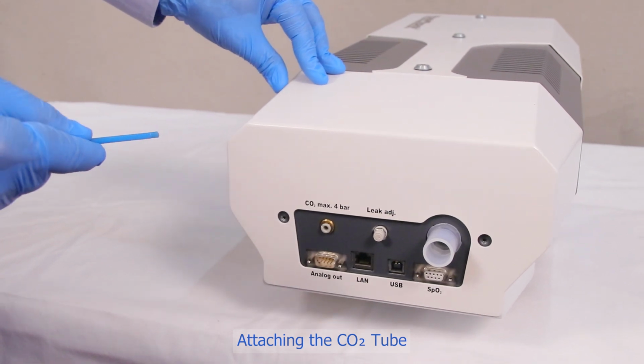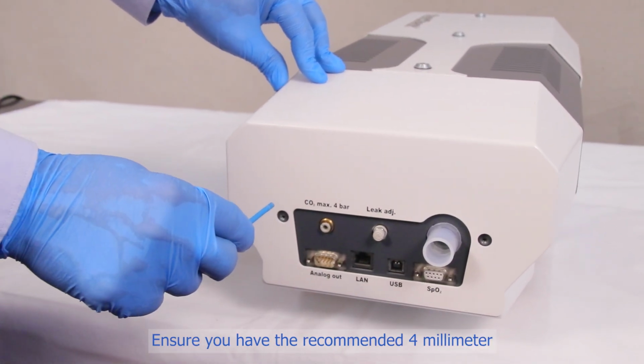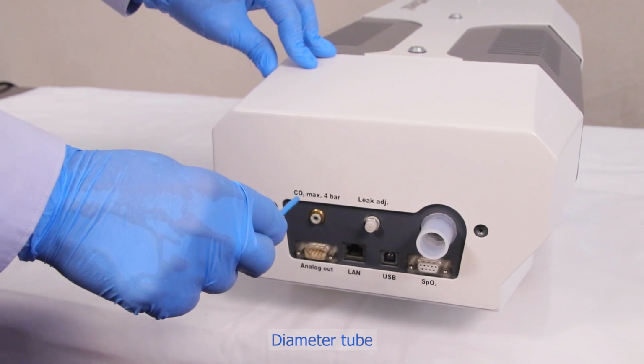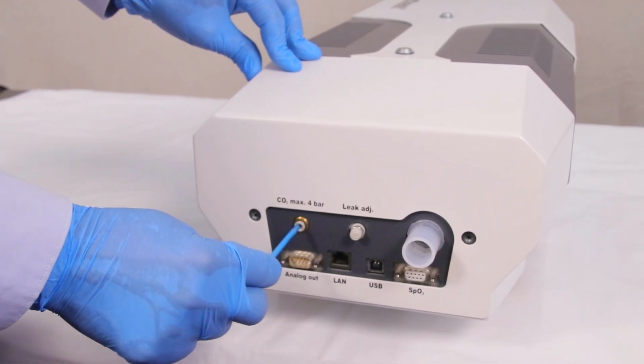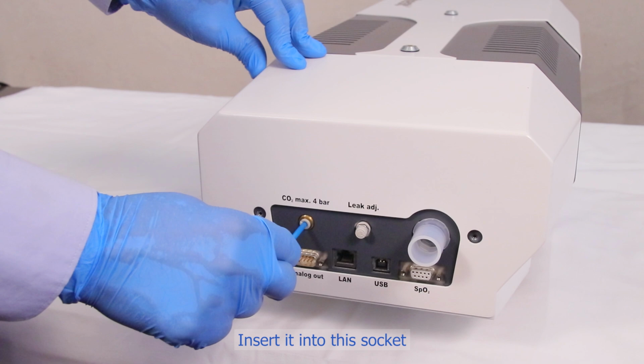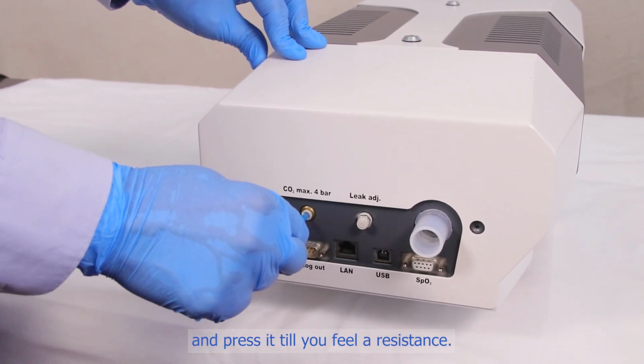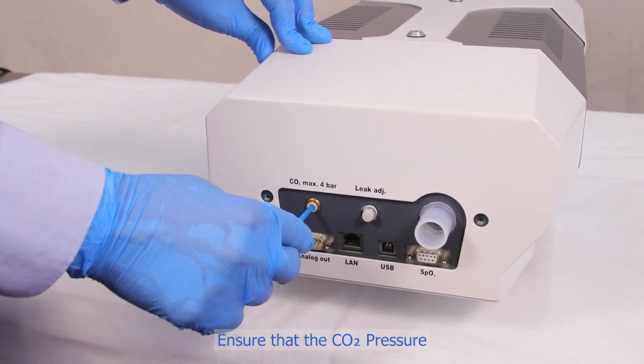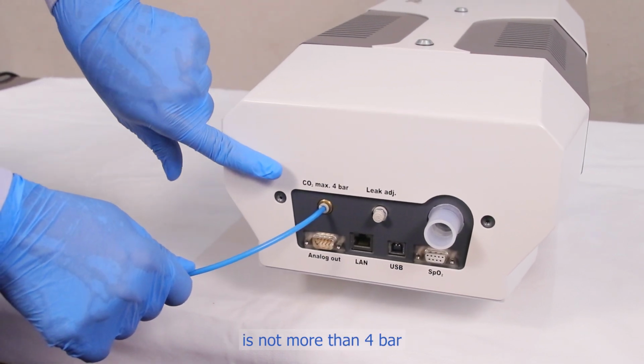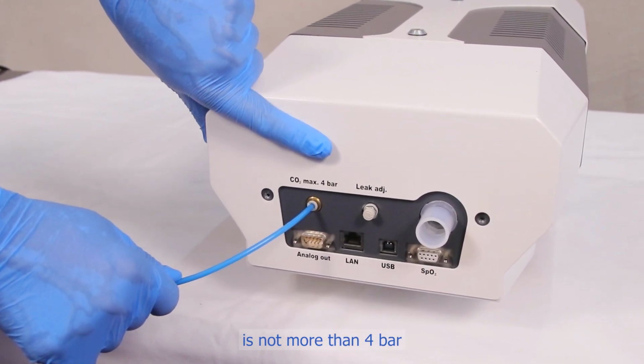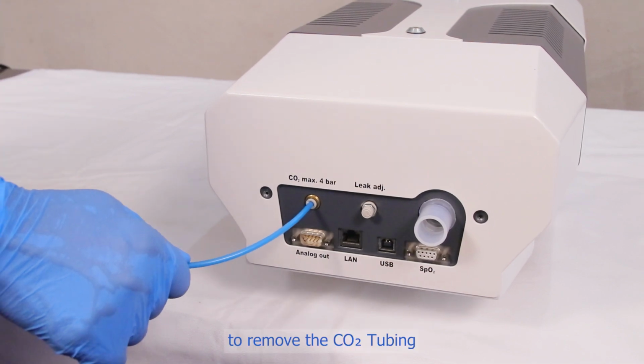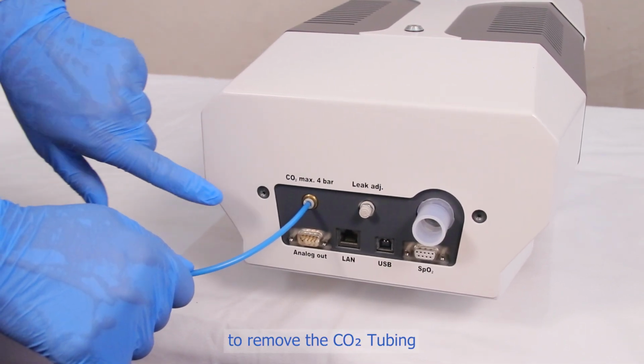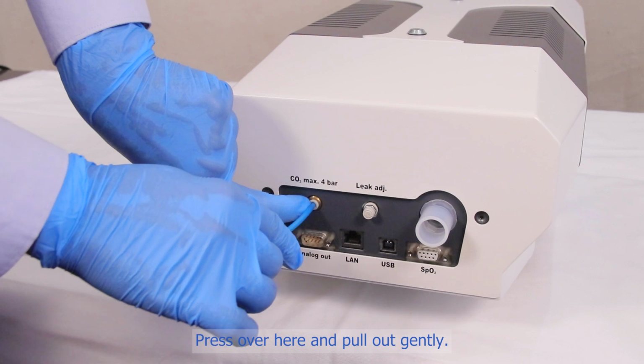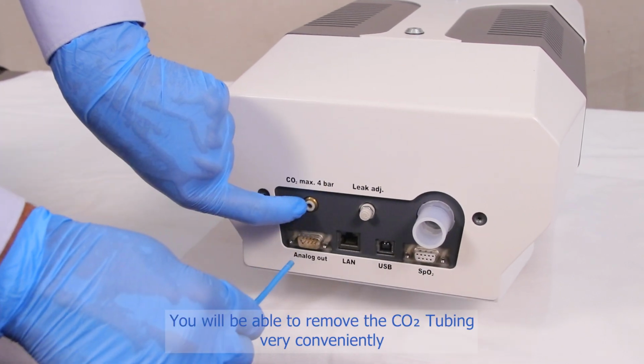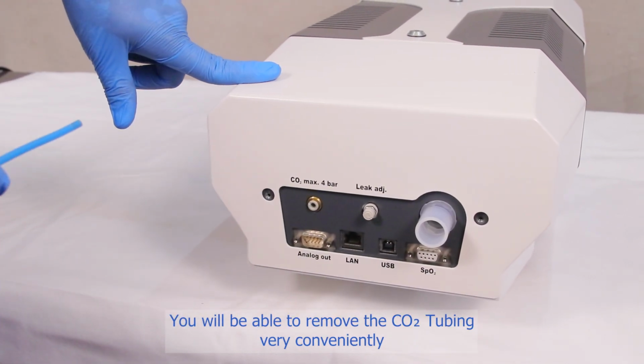Attaching the CO2 tube. Ensure you have the recommended 4 mm diameter tube. Insert it into this socket and press it till you feel a resistance. Ensure that the CO2 pressure is not more than 4 bar. To remove the CO2 tubing, press over here and pull out gently. You will be able to remove the CO2 tubing very conveniently.